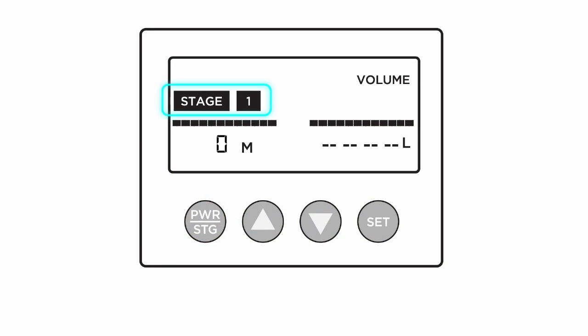Ensure the monitor is highlighting Stage 1. If it is not, press the Power Stage button to cycle through the stages until Stage 1 is selected. Once Stage 1 is highlighted, press the Set button for a second until you hear a beep. The word Set should appear near the upper right corner of the screen. Note that the Set mode will turn off if no buttons are pressed for 15 seconds, in which case the Set button will then have to be pressed again.